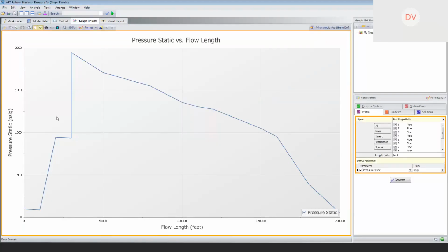Note that if you have pipe that is at 1900 psi, the design of that wall thickness of that particular piece of pipe needs to be able to contain that 1900 psi. That's why this pressure chart becomes very important. And in the design challenge, we've identified for you to be able to have 3 different wall thicknesses of pipe.